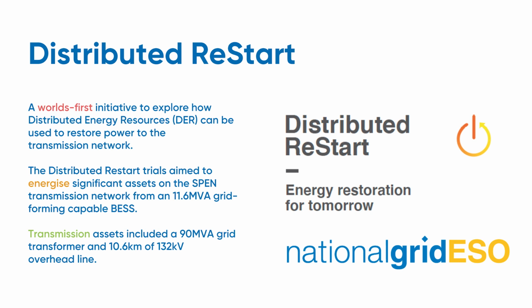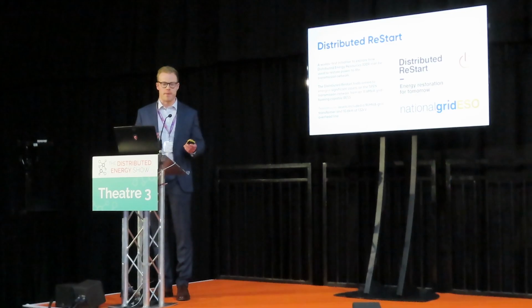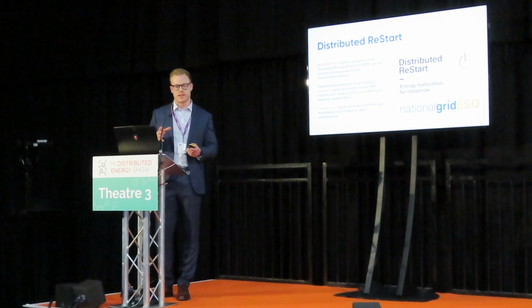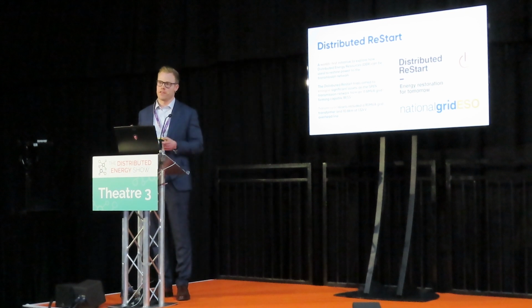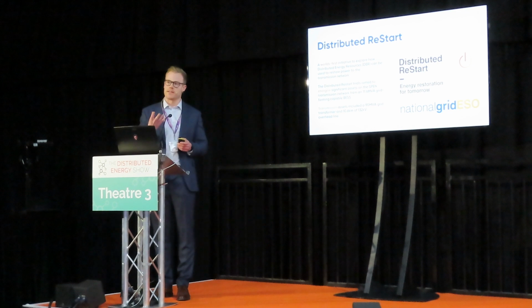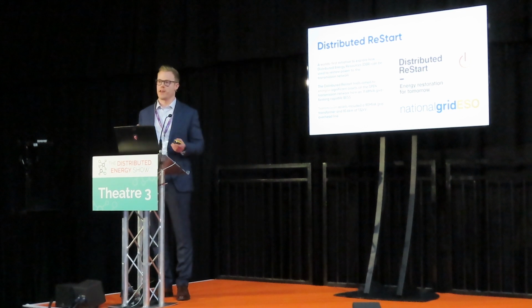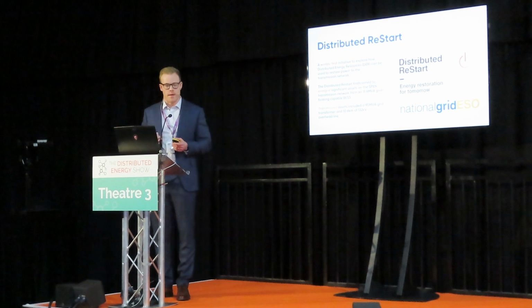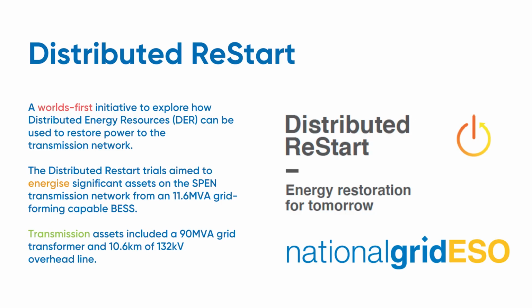Now, this was a world's first initiative, and the idea being they were looking at using an 11.6 MVA grid-forming capable battery energy storage system to actually re-energize large amounts of the Scottish Power transmission network from 33 kV. Now, again, your issue here is kind of flipped in reverse. This time you're trying to energize large assets, but from your small renewable generator. You have the exact same issues we've already discussed. You've got big transformers that are going to be drawing huge inrush currents. You've got big cables going to be drawing inrush currents. We need to find a way to lessen the impact of energizing those so this relatively small battery energy storage system can actually handle that.